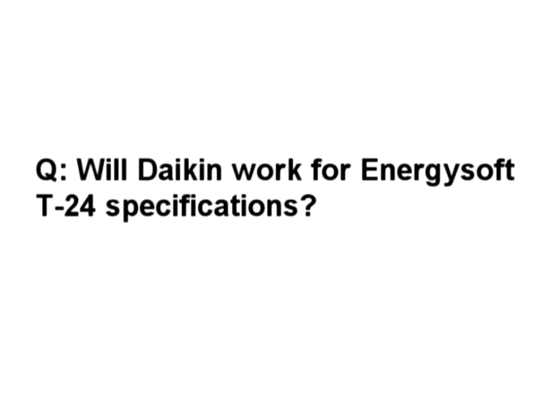Right now, Daikin for the Altherma received a waiver from the DOE about 3 weeks ago. DOE recognized that there is no standard for testing air-to-water heat pumps. So they've agreed to use European testing standards for COP, EER, and for domestic hot water. We're writing that up at this point. It's in the conversion factors. But we know that the COP methodology is the same in Europe as it is here, so we're fine in that regard. In domestic hot water, the conversions for cooling, the EERs on cooling, are taking place as we speak, but they will be above 10. We'll discuss that more in our next session.